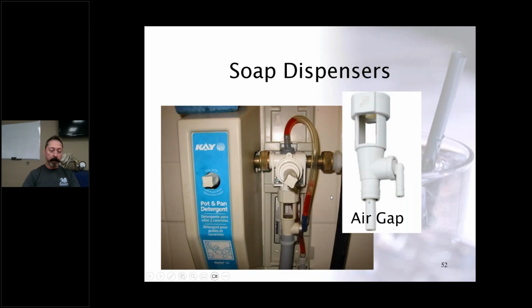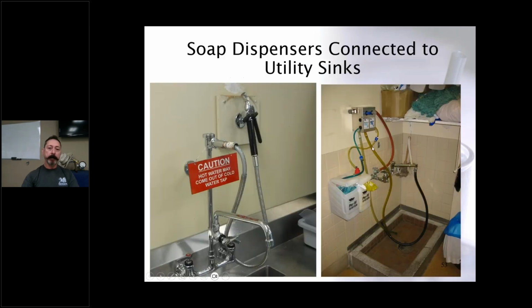Soap dispensers are again everywhere. You'll see those in any janitor room, often connected to the janitor sink, and that will have a built-in integral air gap inside. Hopefully not all of them do, but that's what we want to see. You'll often see soap dispensers connected to the utility sink, and it's actually not the correct way to do that. They should have a designated supply. Otherwise, what you end up with is hot water back pressuring across into the cold water supply.